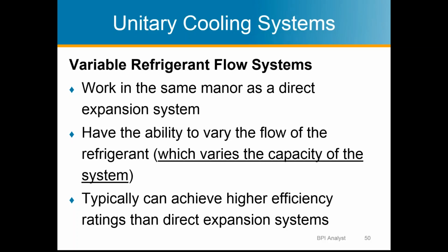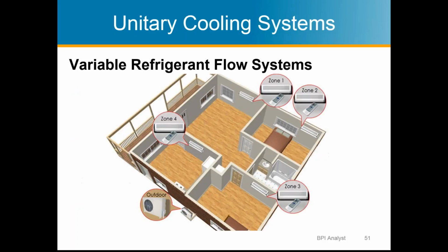So it keeps people more comfortable. You don't cool the house down and then it gets hotter and then it cools back down. Now with the variable refrigerant flow, you can just maintain a temperature without it cycling on and off all the time. Typically, variable refrigerant flow systems can be quite a bit more efficient than a standard constant volume system. Variable refrigerant flow SEER ratings can easily be 16, 18, 20, or more. So they're very efficient.